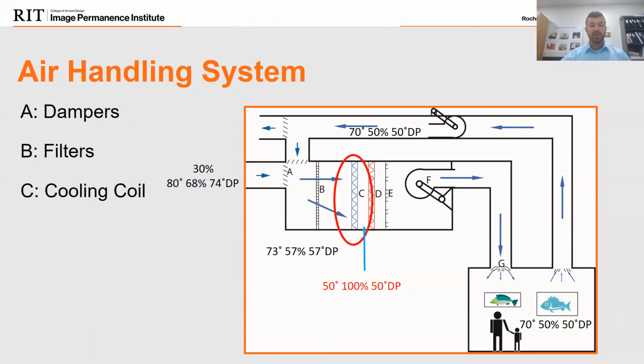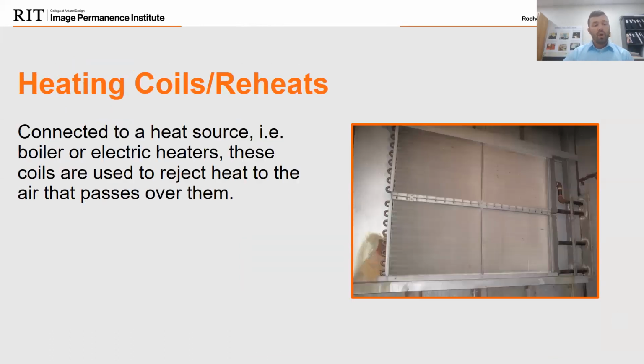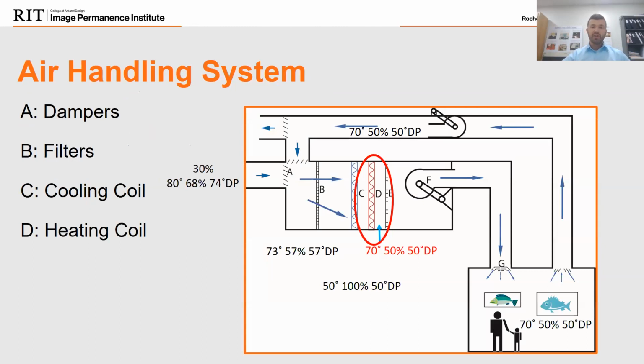Our next stop on this unit is going to be our heating coil. Our heating coil is a source of heat, which can be boilers or electric. When you talk about heating the air, the coils are actively rejecting the heat that's on them to the air that passes over them. So as the air goes over, the coil is rejecting that heat to that air, and we will have our condition. We've heated the air only 20 degrees. We've done no other work. All we have done is heat that air. If you play with a two-point calculator, or if you're aware of a psychrometric chart, as we increase temperature, we reduce the relative humidity. So by adding 20 degrees of temperature, we have brought the relative humidity back down to about 50%.